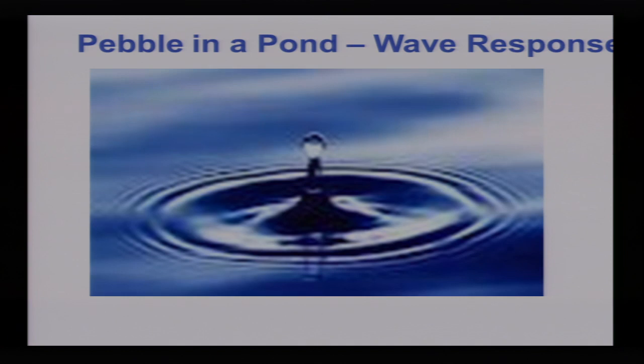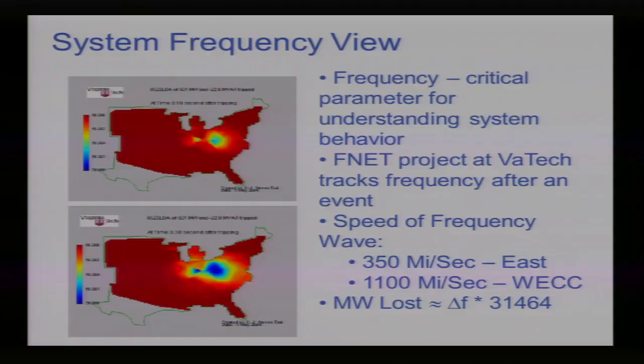It's a function of the viscosity of the liquid in which I drop the pebble. Well, it turns out the power system is very viscous also. When you drop a power plant off the power grid, what happens to the frequency there? At that very center point, it's going to go to zero, of course, because the generator trips offline. But it sends out a ripple of frequency. And what you're looking at here on these diagrams is that ripple spreading out from the center of where the power plant went out. This frequency is a wave. On the East Coast, it travels at 350 miles per second. On the West Coast, it travels at 1,100 miles per second. Why? Much, much longer lines with fewer interconnections and the like.